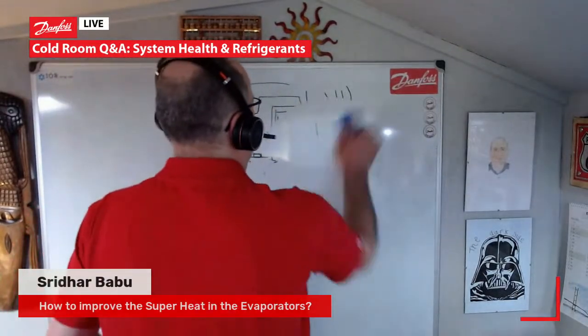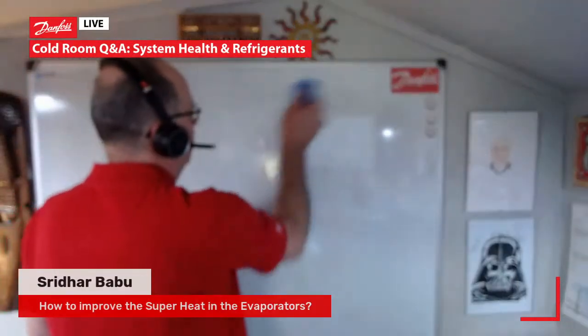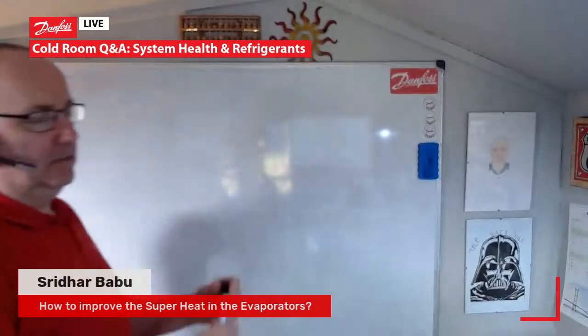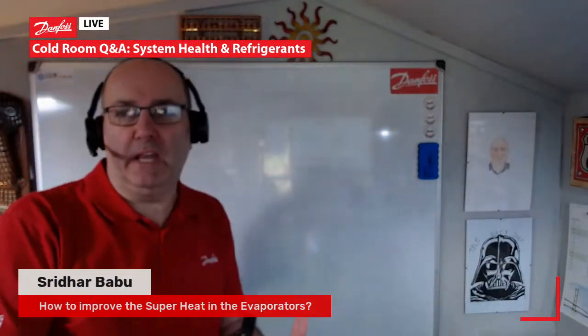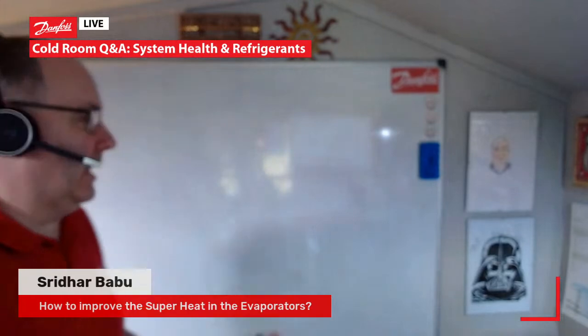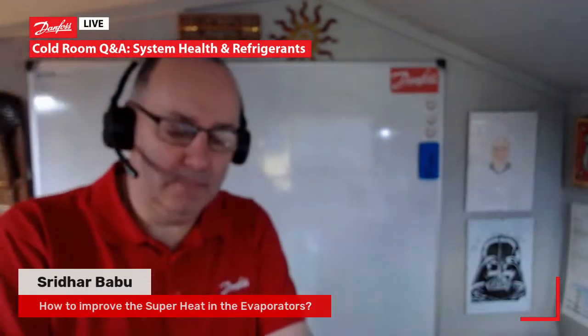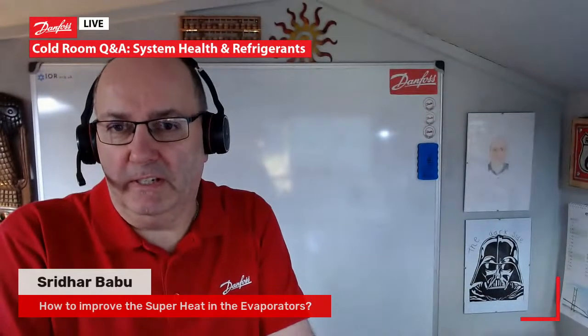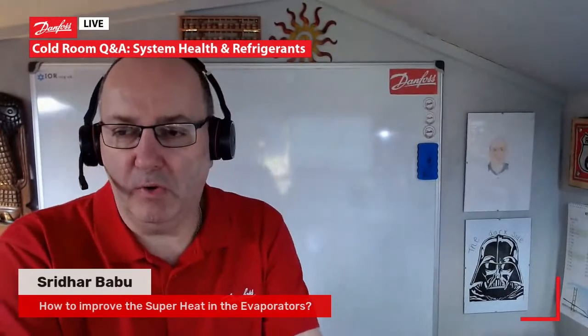Another question's come in, and sorry for my pronunciations of your names, so apologies for that. Okay, so how to improve the superheat in the evaporators? Well, in simple terms, as we said in one of the drawings that I did previously, the more liquid we can feed into that evaporator, the more capacity we get out of that evaporator. How to improve the superheat? Well, we need to get good installation of the expansion valve, as we've just done. Make sure everything's reading right.